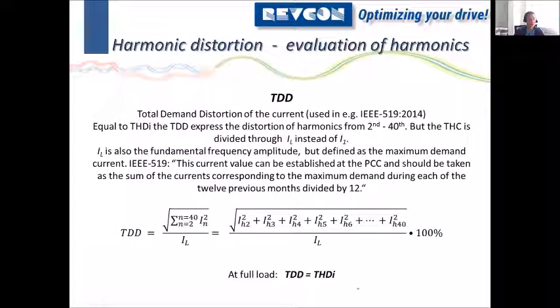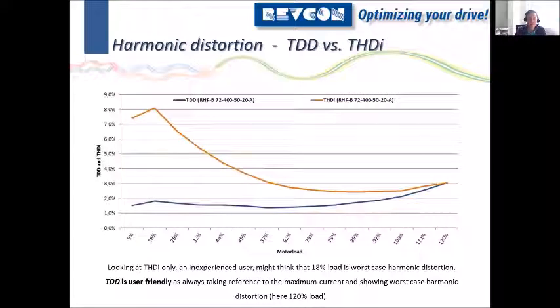So if we look at the full load, the TDD and THDI, full load means the highest value, then we can assume that these two values are the same. And that's a good thing because we should always focus on the maximum power when we speak about THDI. We should not get tricked by someone saying that you should have maybe below 5% at 80% load. That's really nonsense because you don't need that. And I think the IEEE takes that into account and makes a really user-friendly way to handle the harmonics.